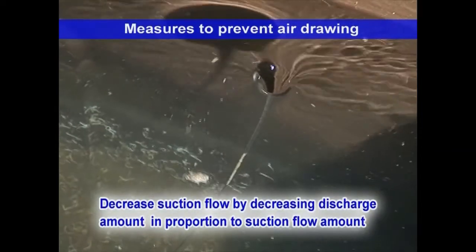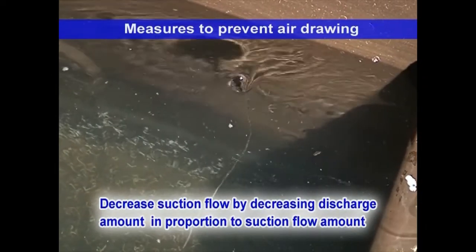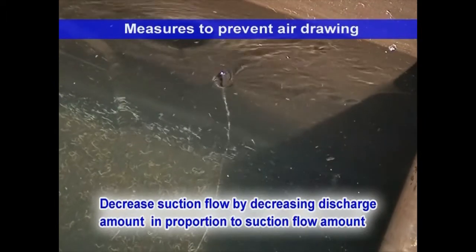To deal with air drawing due to a suction vortex at the bell mouth, decrease the suction flow from the bell mouth by reducing the discharge valve opening to decrease the discharge amount.